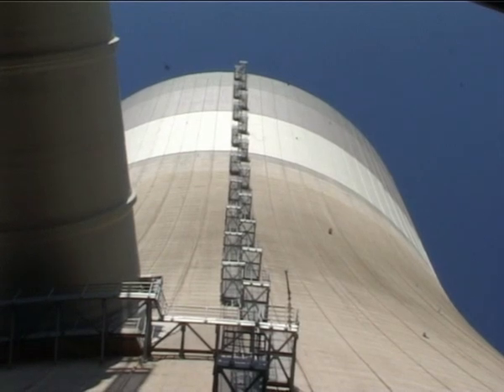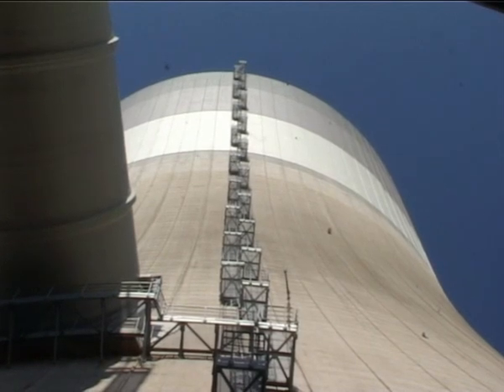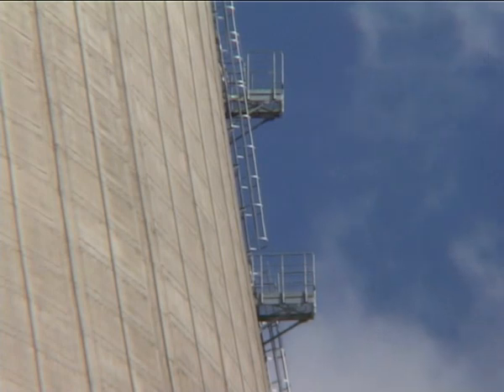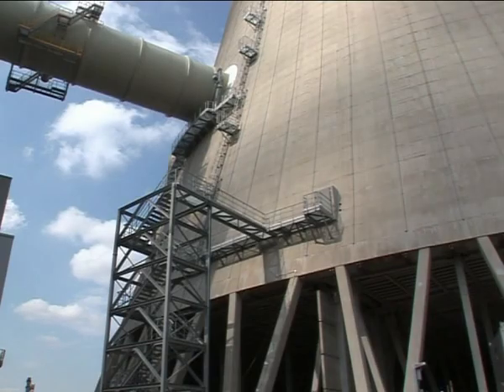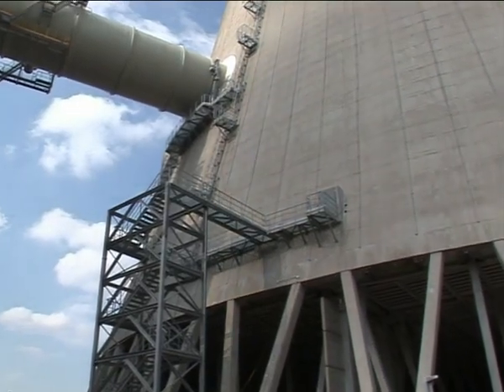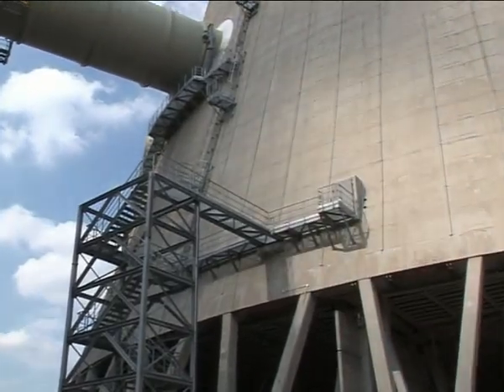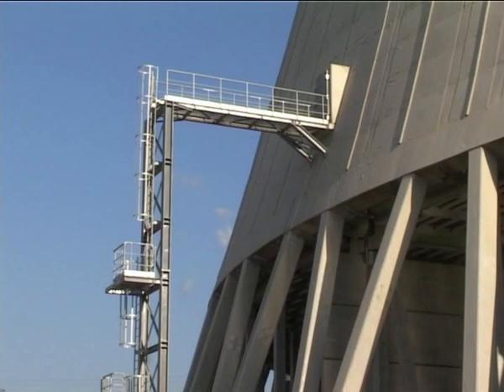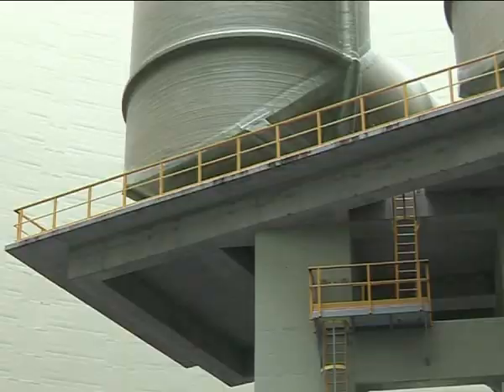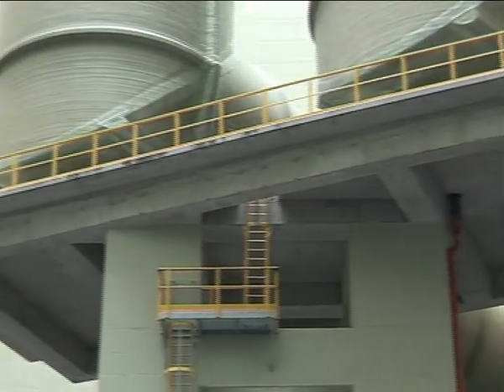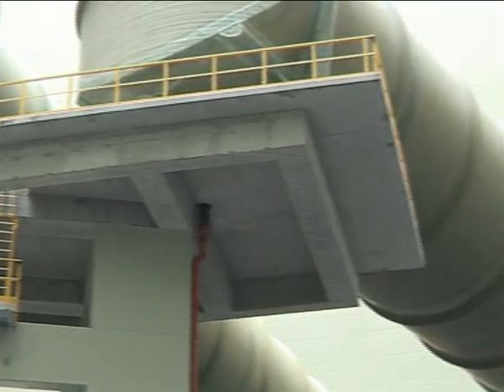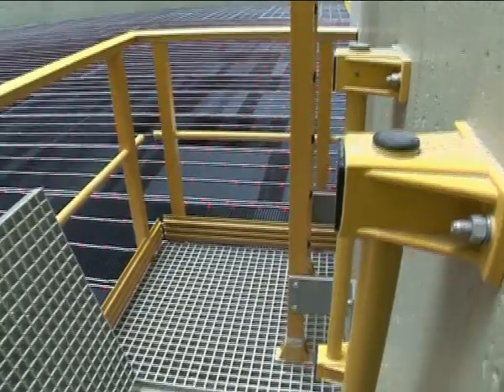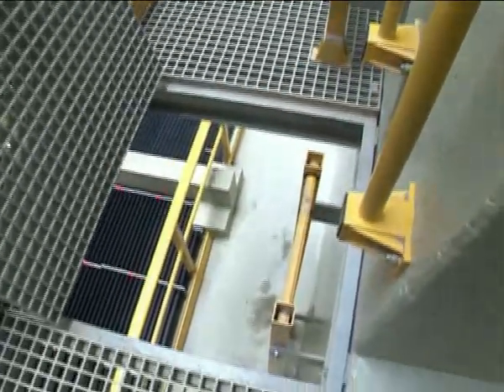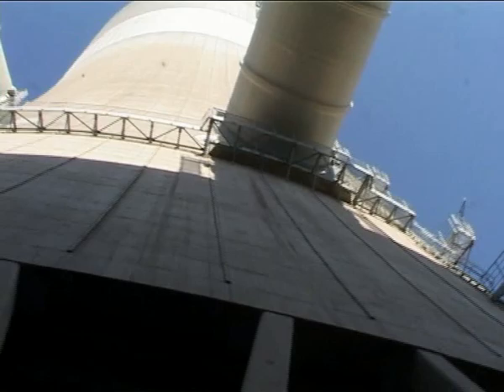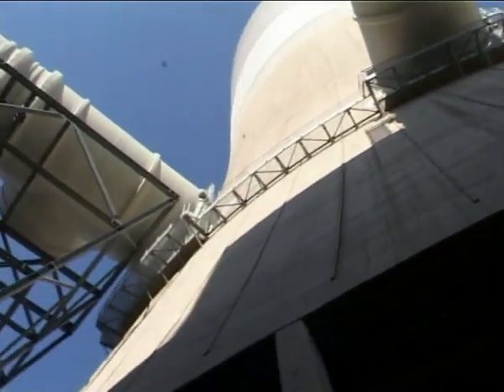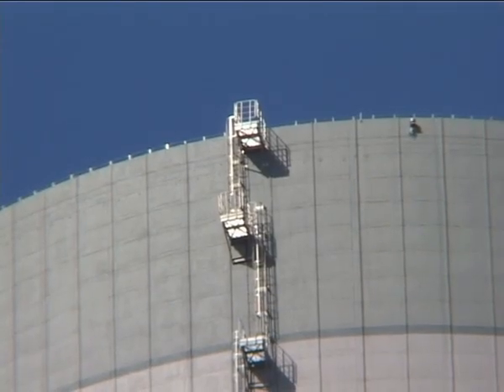Access to the top of the cooling tower is provided by a ladder with resting platforms built every 8 meters. The water distribution level can be reached thanks to a staircase on the south side and a ladder on the north side of the structure. The ladders and railings inside the cooling tower are made of polymer blends to ensure complete elimination of the risk of corrosion. External ladders and galleries, on the other hand, are made of galvanized steel and in the top part of acid-proof steel.